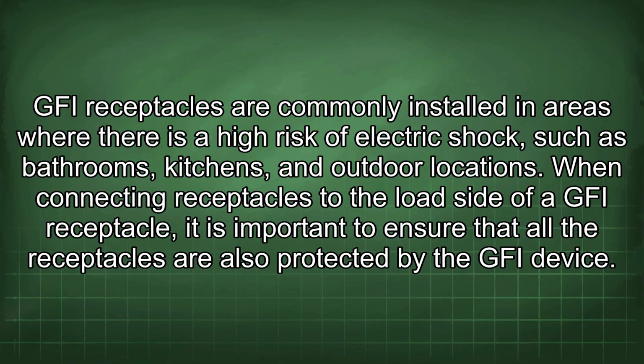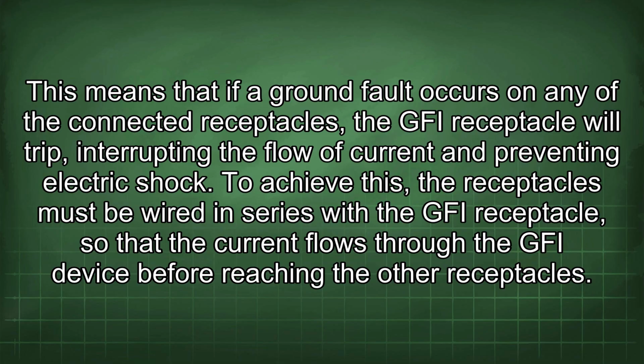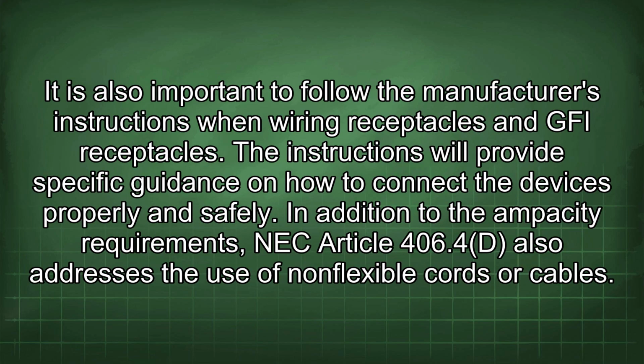When connecting receptacles to the load side of a GFI receptacle, it is important to ensure that all the receptacles are also protected by the GFI device. This means that if a ground fault occurs on any of the connected receptacles, the GFI receptacle will trip, interrupting the flow of current and preventing electric shock. To achieve this, the receptacles must be wired in series with the GFI receptacle, so that the current flows through the GFI device before reaching the other receptacles. It is also important to follow the manufacturer's instructions when wiring receptacles and GFI receptacles. The instructions will provide specific guidance on how to connect the devices properly and safely.